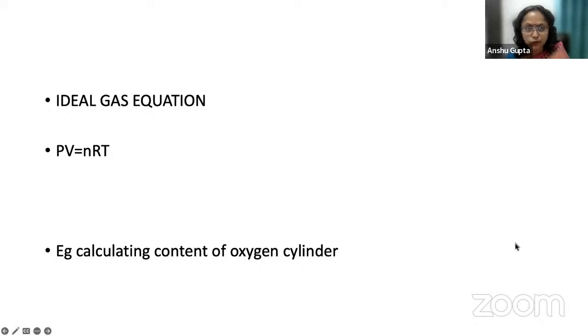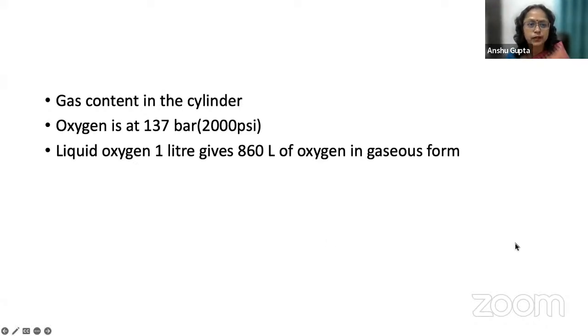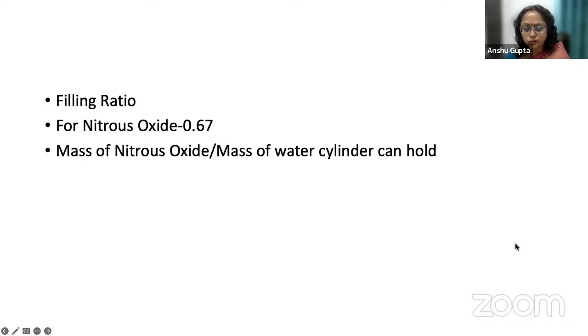But is it true for all cylinders? We'll see later. Regarding gas content, when it is liquid oxygen, 1 liter of liquid oxygen gives rise to 860 liters of oxygen in gaseous form. Normal pressure in the cylinder is 137 bar. Now suppose we have a nitrous oxide cylinder. Here the nitrous oxide is in liquid form. The problem is that the pressure gauge gives us the pressure of the cylinder. In oxygen, we said that as the cylinder gets exhausted, pressure will come down. But with nitrous oxide, it is in liquid form with some space which is left.